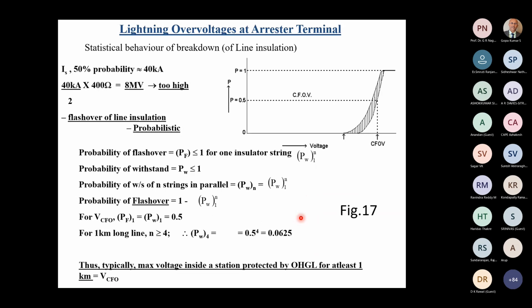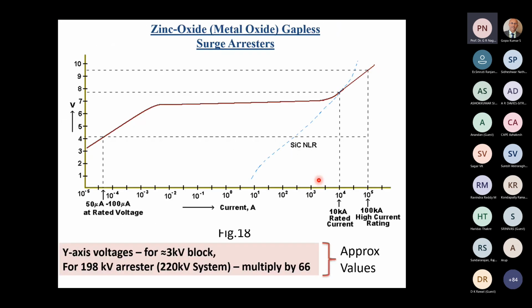So now, the probability of the current we have seen is 40 kA, 50% probability value. So 8 megavolts is too high. So the critical flashover level of the insulator string tends to travel to the power station along the line. It causes flashover of the first insulator string. If it does not, the next one. If it does not, the next one. Like that, there are a number of insulator strings in the way. One or the other of them will cause flashover. So the voltage that finally appears is equal to the 50% probable flashover level of the insulator strings. That's what we call the critical flashover voltage level. That gets reduced considerably. That's the voltage which comes across the transformers in power stations.